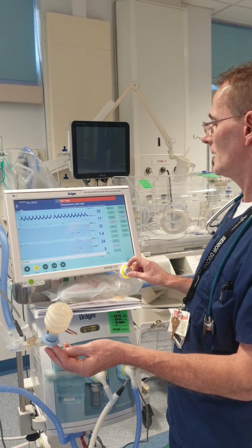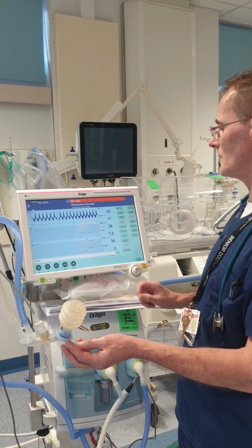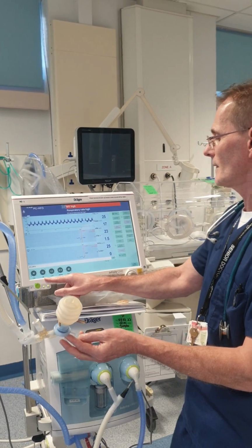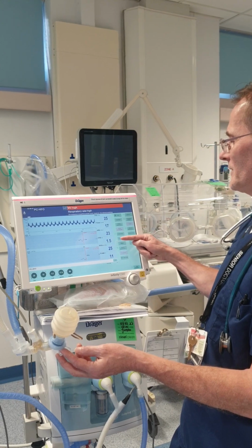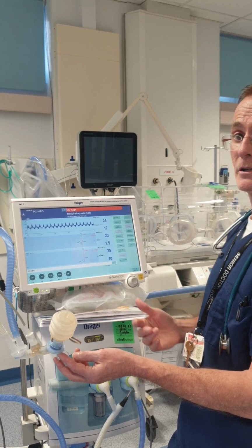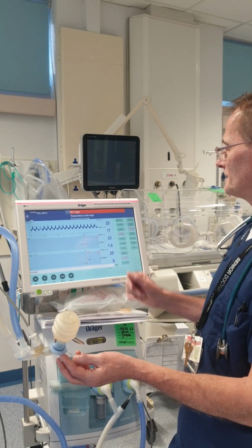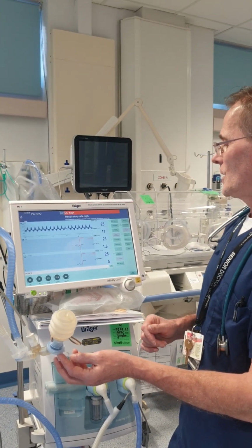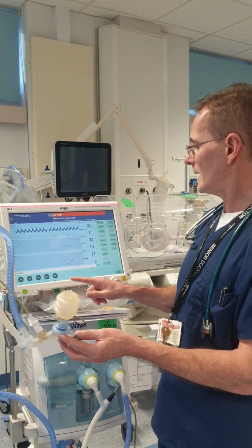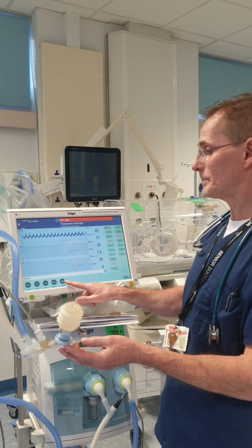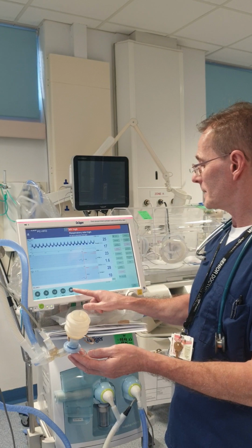Let's say I still want to get to 2 mils per kilogram. I'll drop the frequency again. And let's see how we're achieving this now. This is a dummy lung, so it's not entirely physiological. That's maybe as good as it can get, but it's gone up. So manipulating CO2, once you've got your lungs open, the most important thing is to manipulate your amplitude. That's the chest wiggle factor, and that's by manipulating the amplitude.